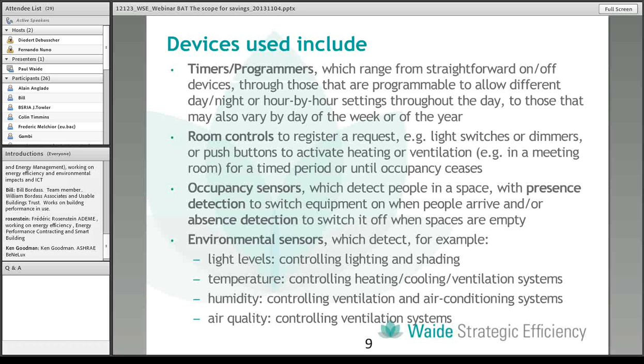As part of the Energy Performance in Buildings Directive technical effort, which involves building a large suite of European standards to enable whole energy performance to be calculated and derived, a standard was developed, EN 15232, to provide guidance on how to include building automated control and building management within the whole building energy impact assessment method developed by the EU. This includes a detailed list of the control, building automation, and technical building management functions which have an impact on building energy performance.